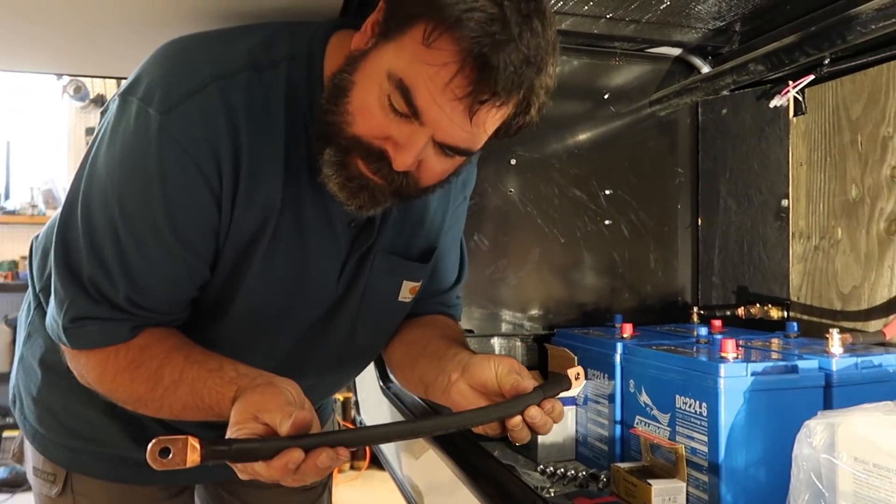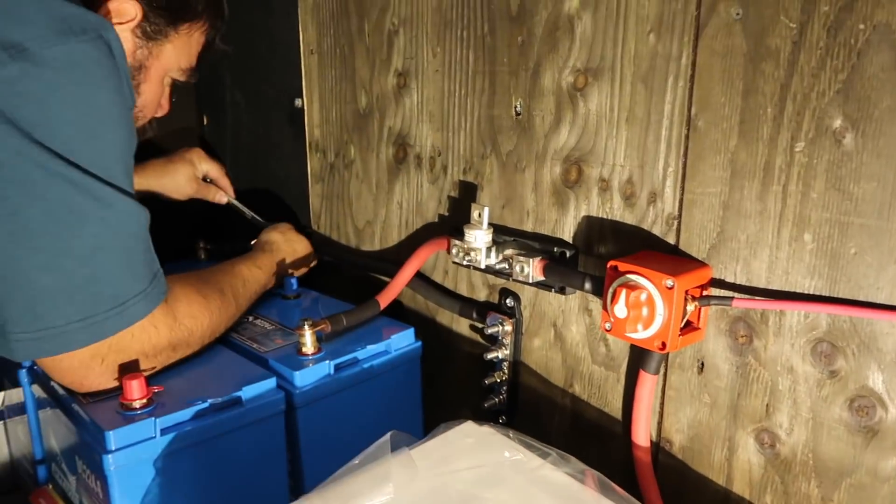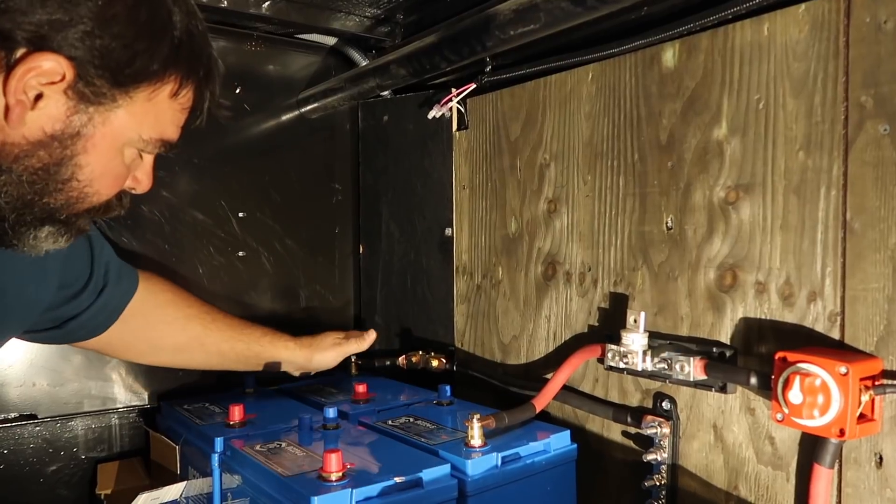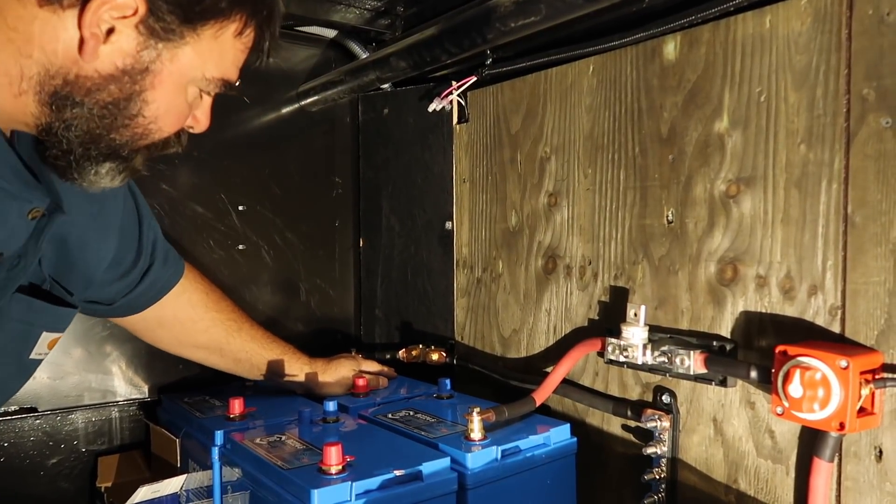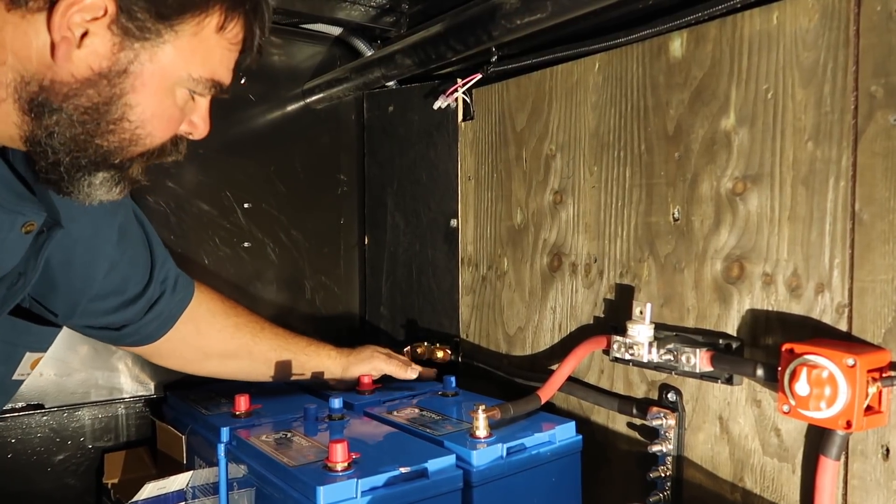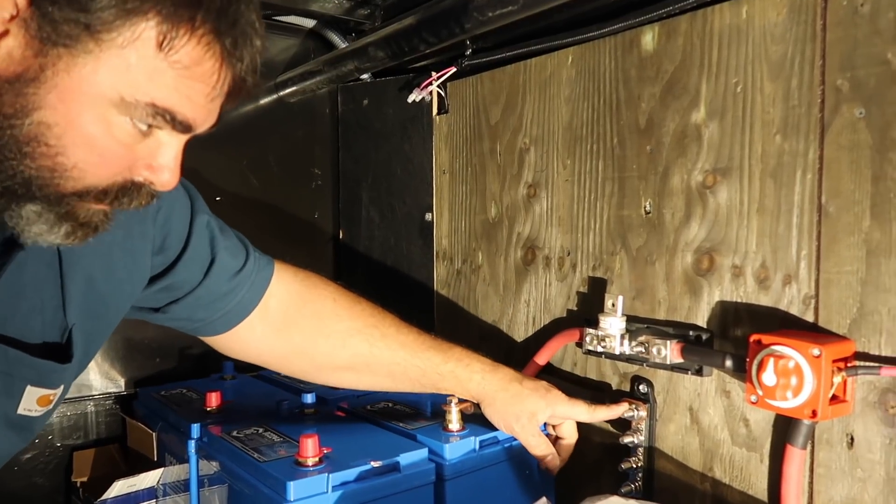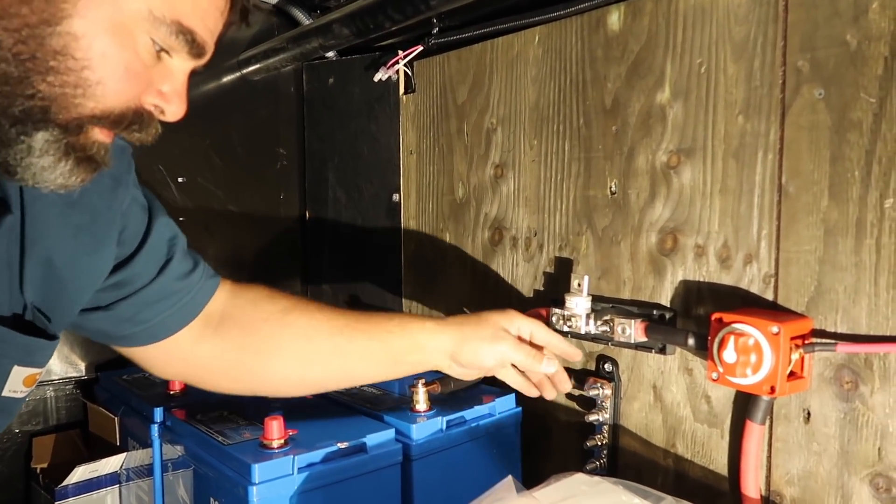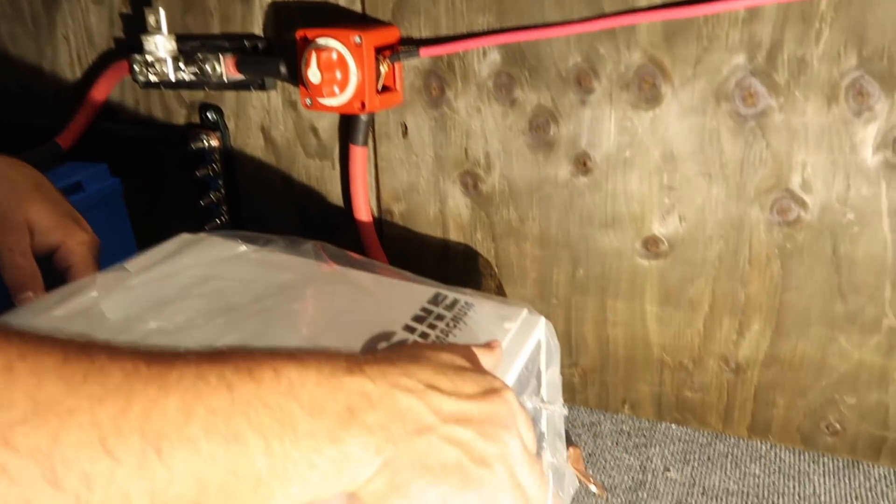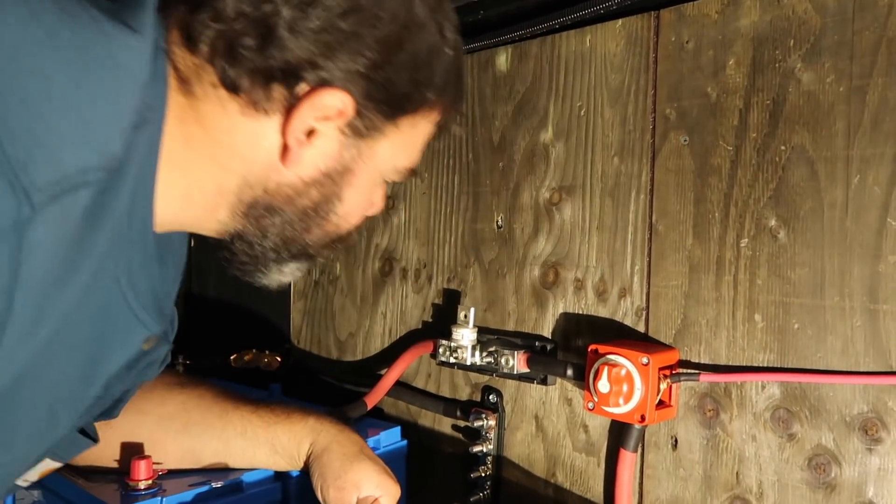That'll be great. Alright, that's all done up right there. And it's the right size? Hey, let's find out right now. Yep, now I've got the batteries hooked directly up to the shunt. This is for the battery monitoring kit. And then the negative from there goes to my negative bus bar. And now I need to run a negative four aught to the inverter.